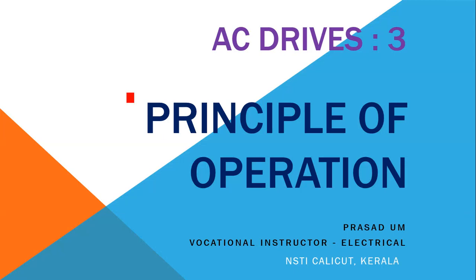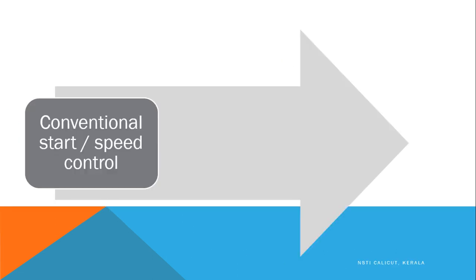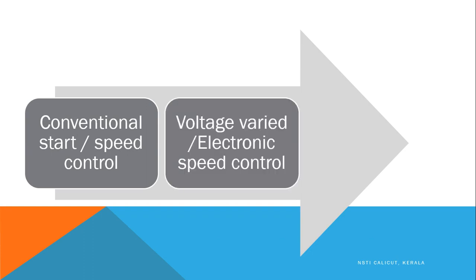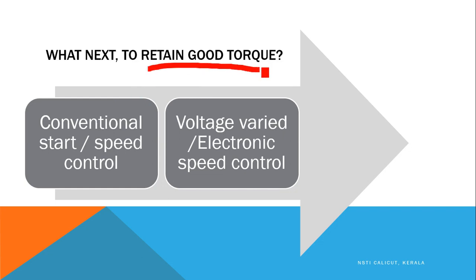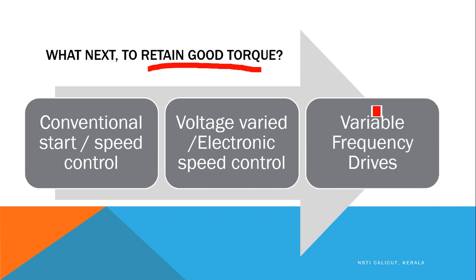AC drives part 3 video. Today we will be discussing the principle of operation of AC drives. We have made two videos before - the first was about conventional starting and speed control methods, and the second was the voltage varied method using a resistance regulator or triac regulator for ceiling fan type motors. Both methods have an issue with torque: when the voltage is reduced, the torque reduces. Torque is an essential component for every motor, so bigger power motors cannot be controlled with voltage variation. To retain good torque, we use variable frequency drives or AC drives.